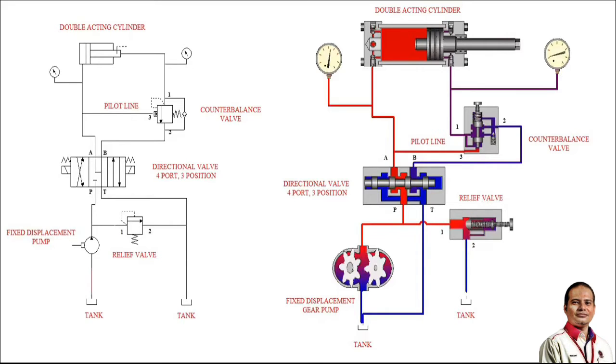Now another interesting thing between those last two frames is we see our relief valve open back up again. So I'll go back a frame, and you see the relief valve was closed when things were moving along, and then I advance it, it opens up again. So I'll go back again and advance, back and advance, so you can see that relief valve opening up, because now all of a sudden the only way this pump can relieve itself is to elevate its pressure to the setting of this relief valve and go to tank.